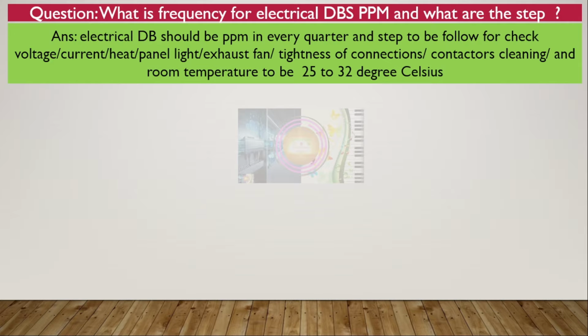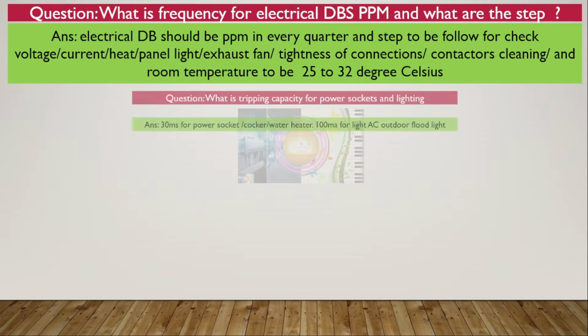So question: what is the frequency for electrical DB PPM and what are the steps? Electrical DB should have PPM every quarter, and the steps to follow are to check voltage, current, heat, panel light, exhaust fan, tightness of connection, contactor cleaning, and room temperature to be 25 to 32 degrees Celsius.